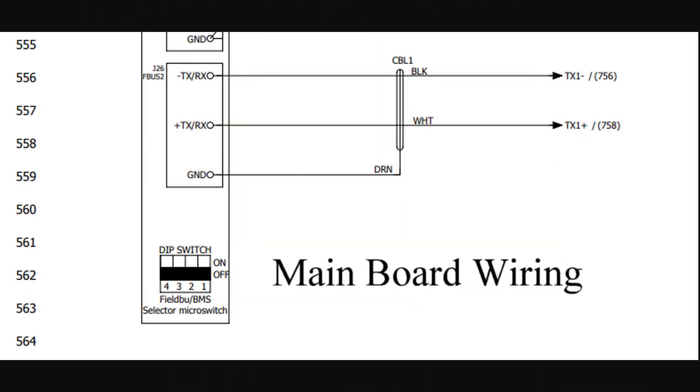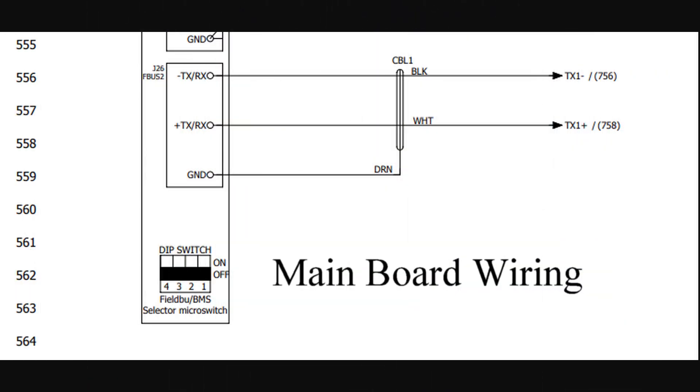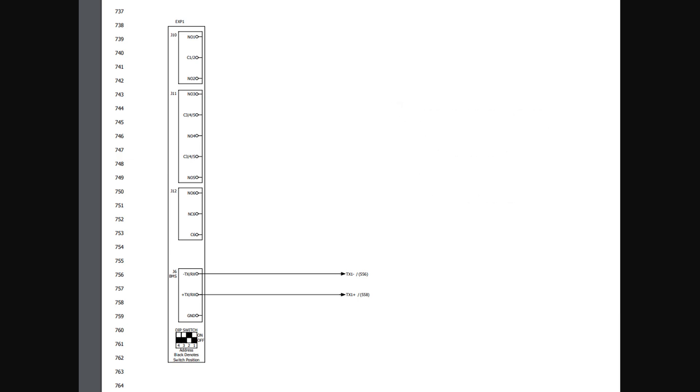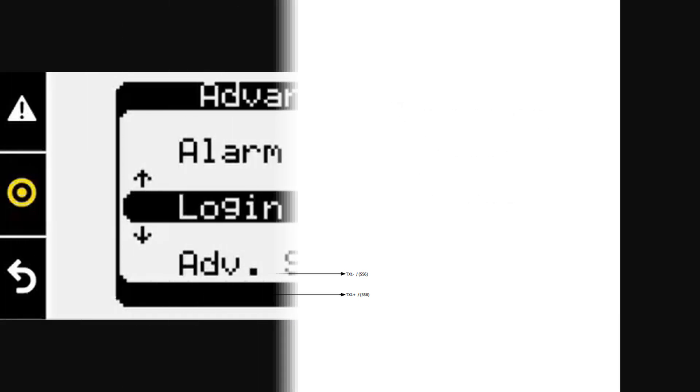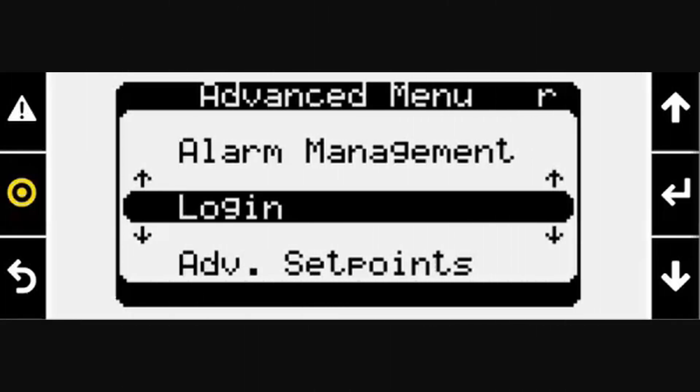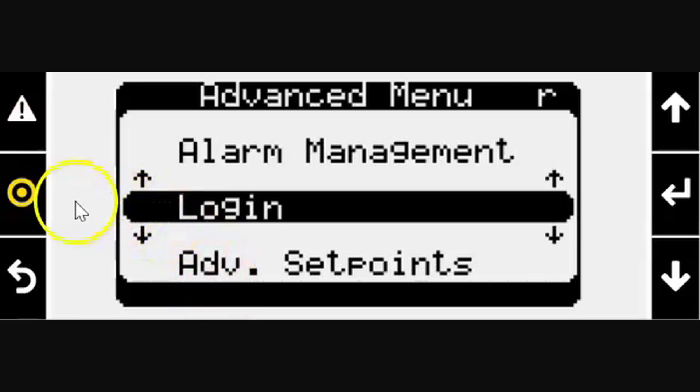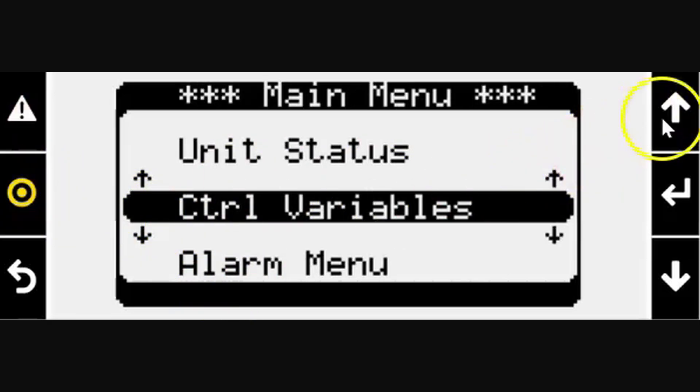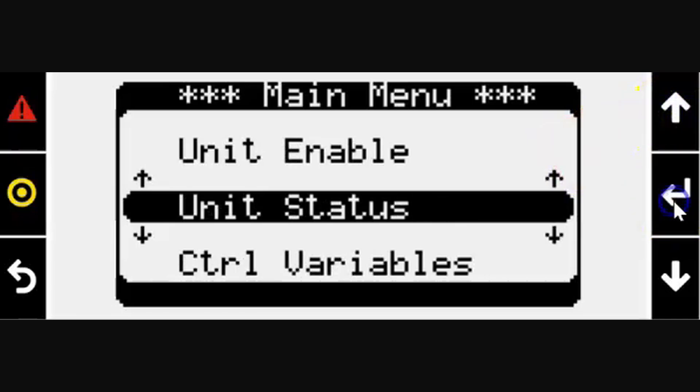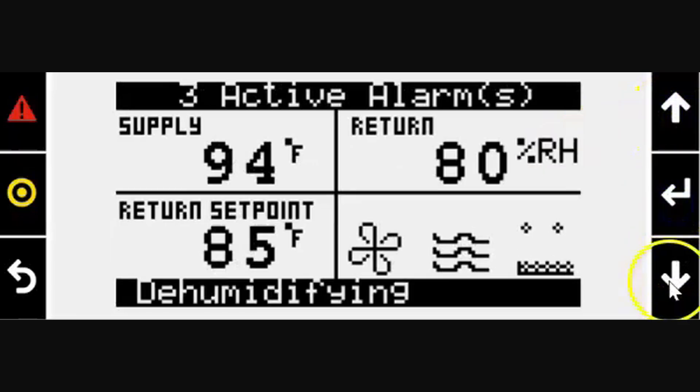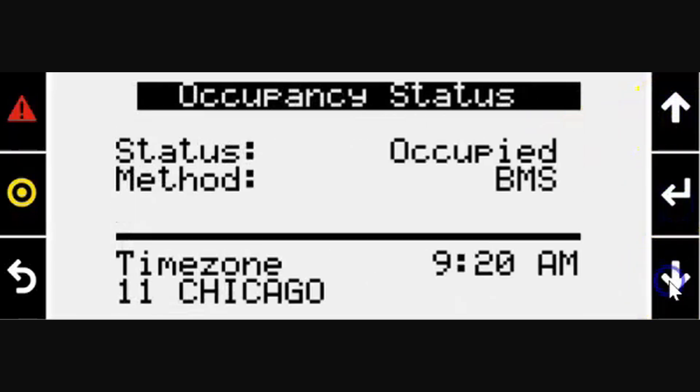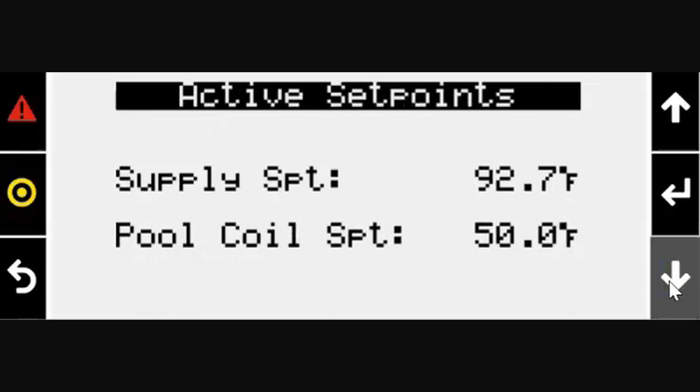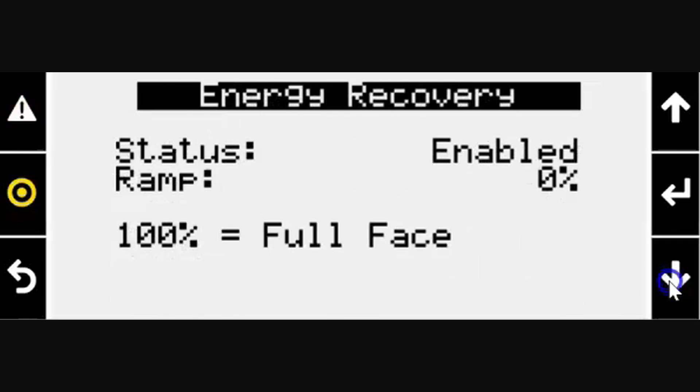Review the unit's wiring diagram to ensure the cables are connected to the proper terminals and be sure to use cables rated for RS-485 communication. The connection of the expansion board can then be verified at the main controller's display. Press the target button and scroll to the unit status and press enter. Scroll to the expansion board status and you should see which boards are currently connected to the main control board.